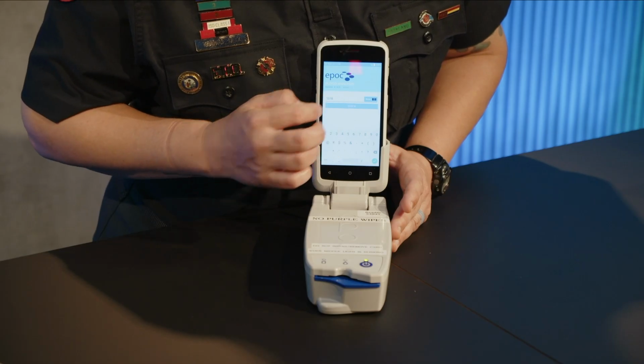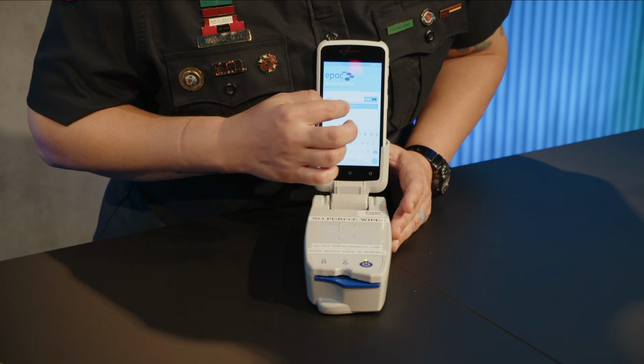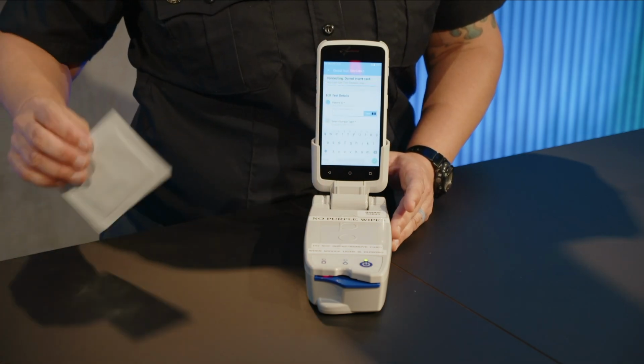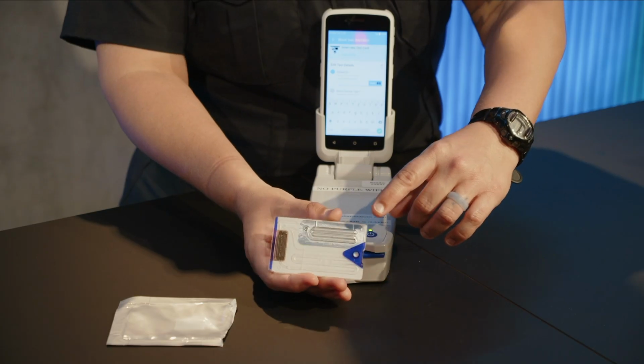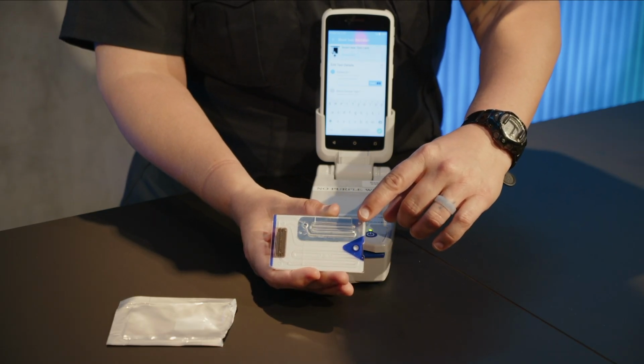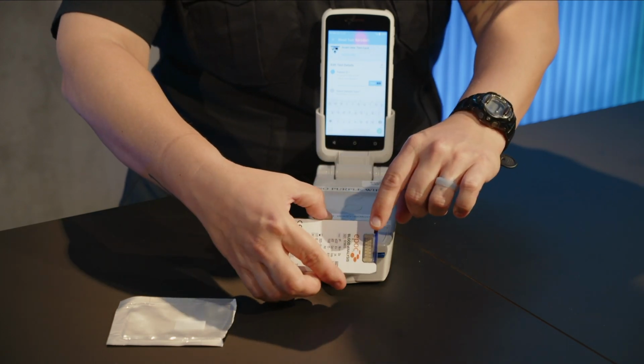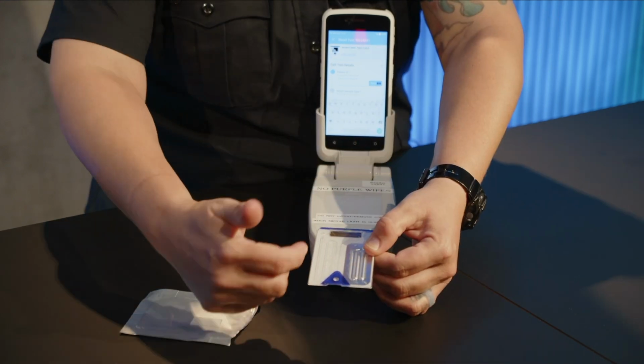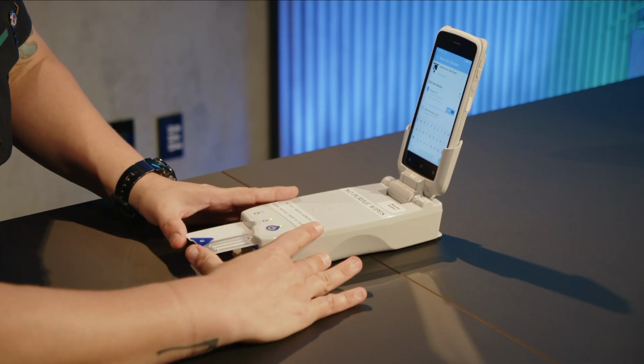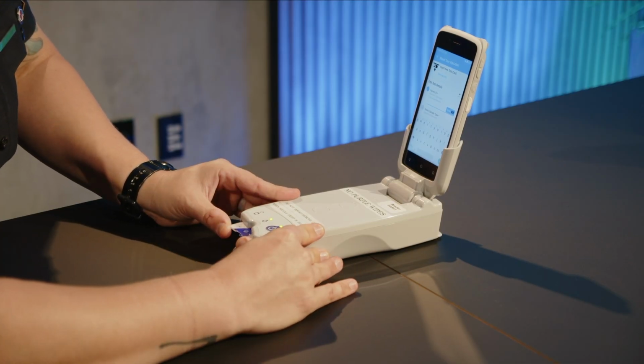Now let's walk through how to perform the test. First, log into the host by entering your user ID and password. Next, grab a fresh test card. When handling the test card, always hold it by the edges. Never touch the calibration fluid or the sensors. Insert the card into the reader with the blue arrow facing up and towards the device. Once started, the calibration process will start automatically. This takes about 165 seconds, so during that time, you can get your patient sample ready.